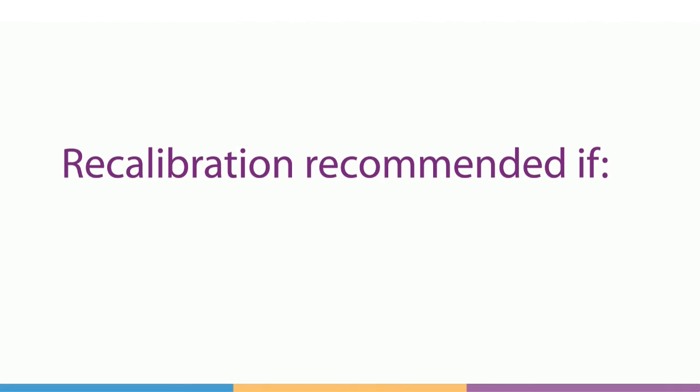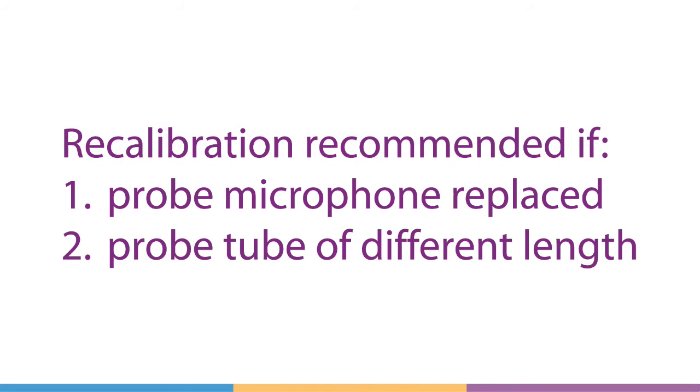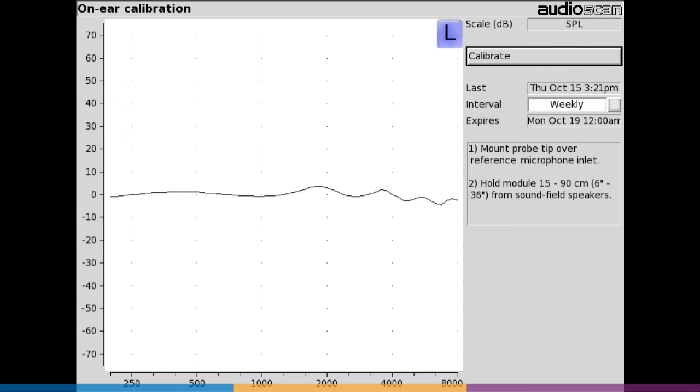You should recalibrate if a probe microphone is replaced or if a probe tube with different dimensions is installed.